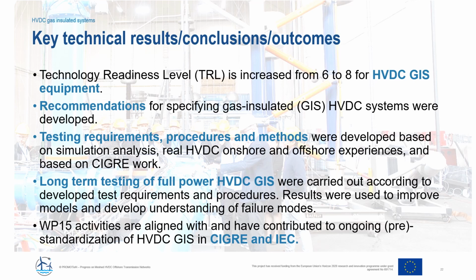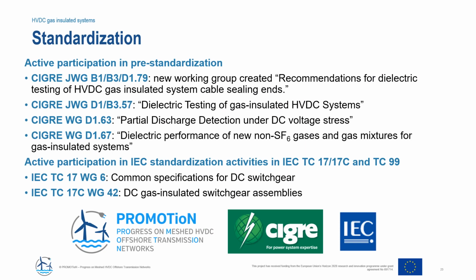Work Package 15 is aligned with and has contributed to ongoing pre-standardization of HVDC GIS in CIGRE and in IEC. The members of Work Package 15 are also very active in standardization and pre-standardization groups, and we have also initiated new pre-standardization work. For instance, the joint working group B1, B3, D1 79 from CIGRE, a new working group about recommendations for dielectric testing of HVDC gas-insulated system cable sealing ends. Moreover, we had a close cooperation with the CIGRE joint working group on dielectric testing of gas-insulated HVDC systems, with D1.63 on partial discharge detection under DC voltage stress, as well as with D1.67 on dielectric performance of new non-SF6 gases and gas mixtures for gas-insulated systems.